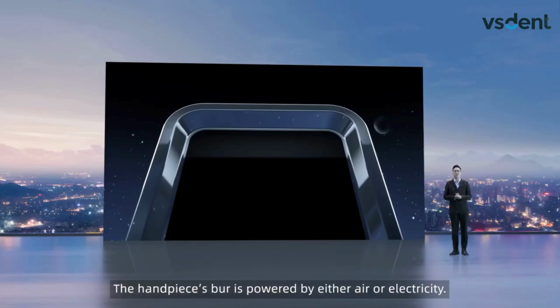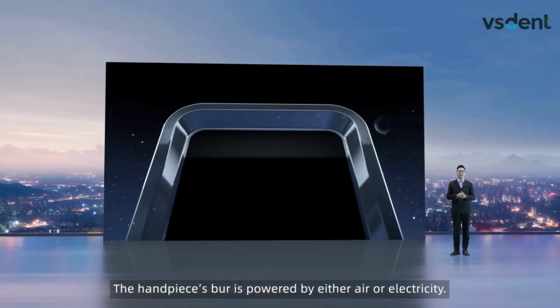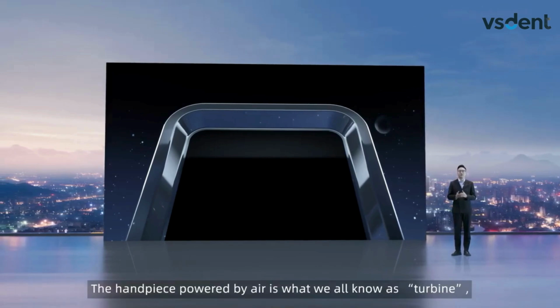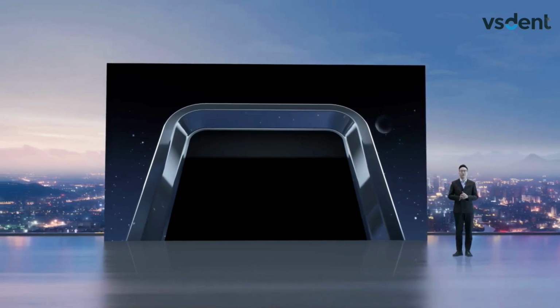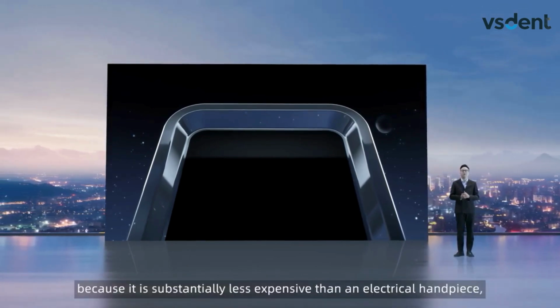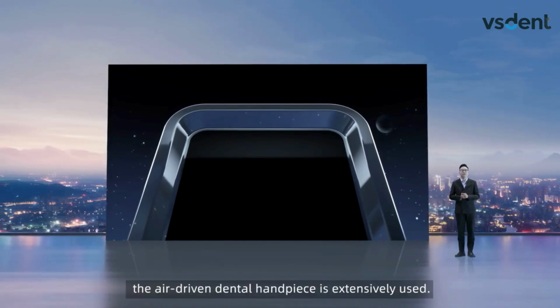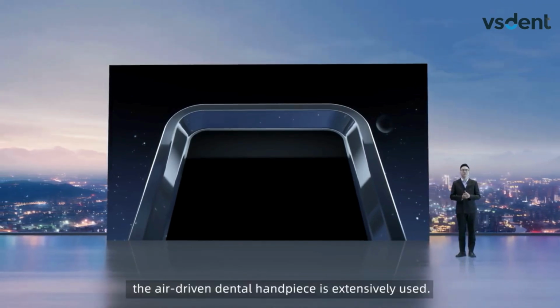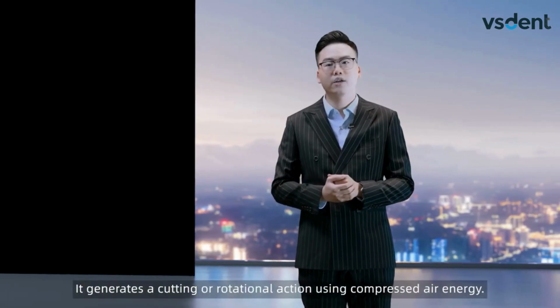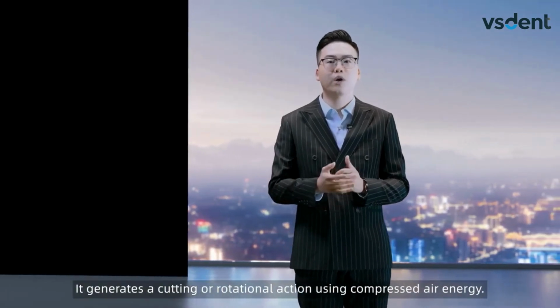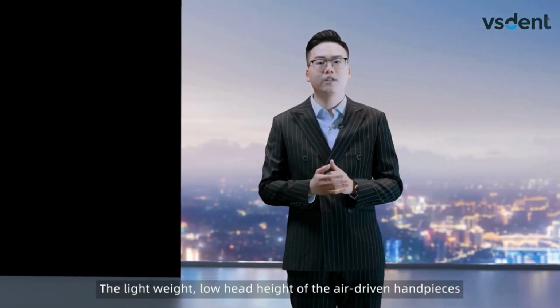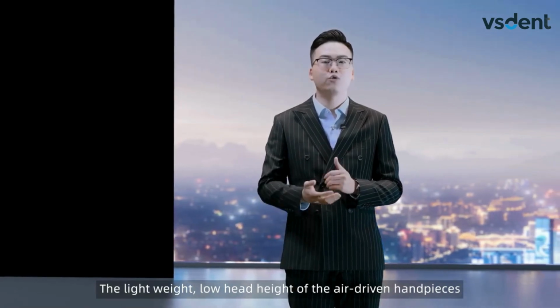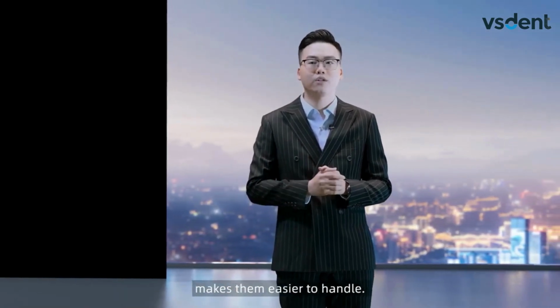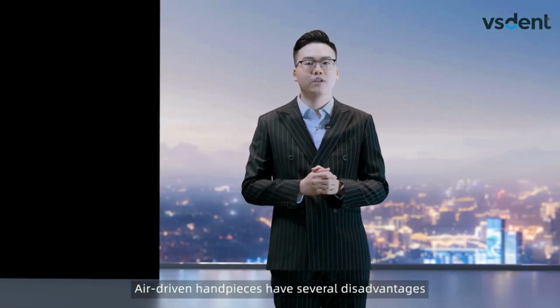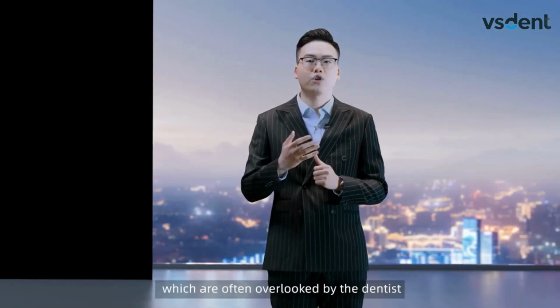The handpiece's bur is powered by either air or electricity. The handpiece powered by air is what we all know as turbine. Because it's substantially less expensive than an electrical handpiece, the air-driven dental handpiece is extensively used. It generates a cutting or rotational action using compressed air energy. The lightweight, low head height of the air-driven handpieces makes them easier to handle. However, air-driven handpieces have several disadvantages, which are often overlooked by the dentist.